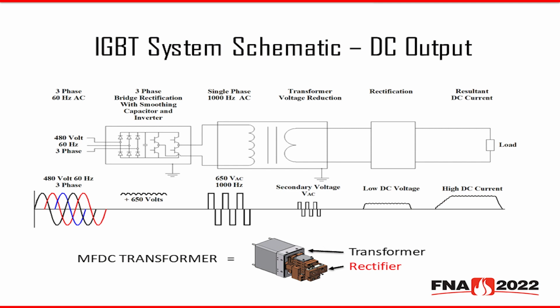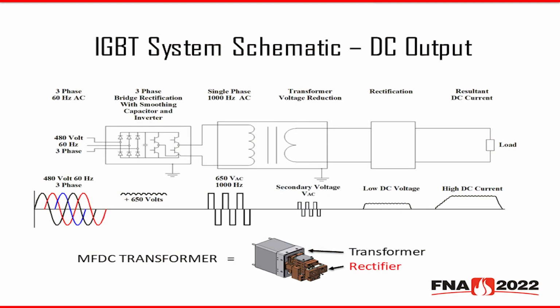The 1000 hertz, 650 volts is then delivered to an MFDC transformer. That steps the low current, high voltage power down to high current, low voltage power. Within the MFDC transformer, there are then diodes that rectify that 1000 hertz AC waveform into low voltage, high current DC power. That DC power is then delivered to the load. At the bottom of the screen, you can see the inner workings of an MFDC transformer, which shows how the rectifier is very closely coupled to the transformer. It's that high current circuit between the transformer and the rectifier that's extraordinarily inefficient.